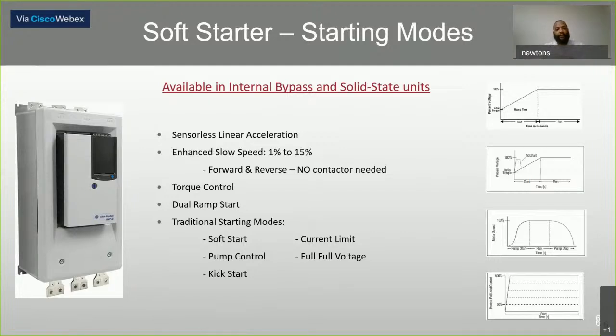Another advantage of having a soft start is that you have the capability to jog your motor in either direction. What does jog mean? A jog is typically, out of the box, running at 10% speed, but with your SMC soft starts, you're able to jog anywhere between 1 and 15% speed in either direction, forward or reverse. Well, how is that so?